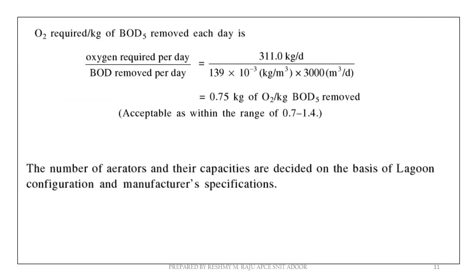We calculate oxygen required per day divided by BOD removed per day: 311 kg/day divided by BOD removed per day. This gives 0.75 kg O₂ per kg BOD5 removed. The acceptable limit is 0.7 to 1.4 kg, so this value falls within the acceptable range. We then consider aeration capacity, power, and configuration for the aerated lagoon design.